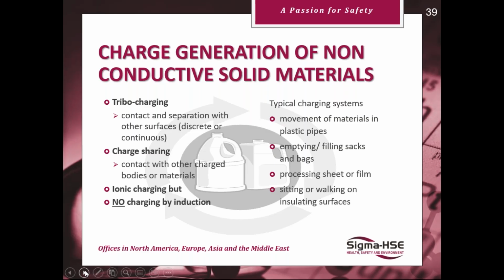Charge generation of non-conductive solid materials: tribocharging is the contact and separation with other surfaces, discrete or continuous. Charge sharing is contact with other charged bodies or materials, where you share the charge with them. We saw that with the balls, for instance. Ionic charging, but no charging by induction.